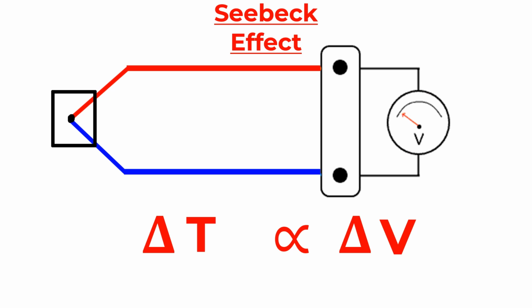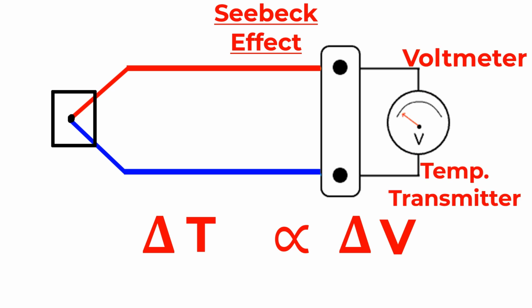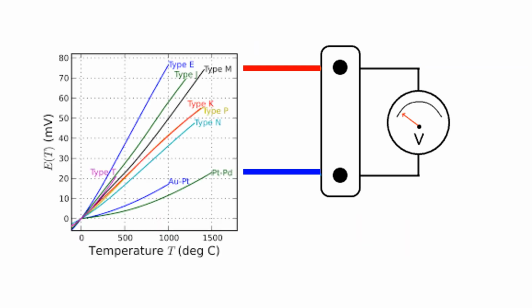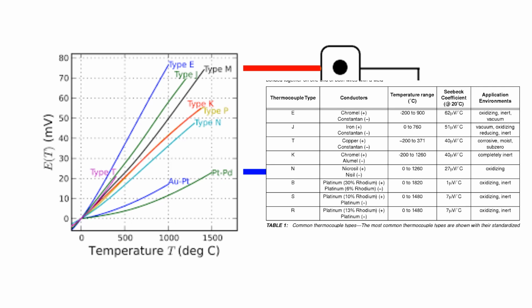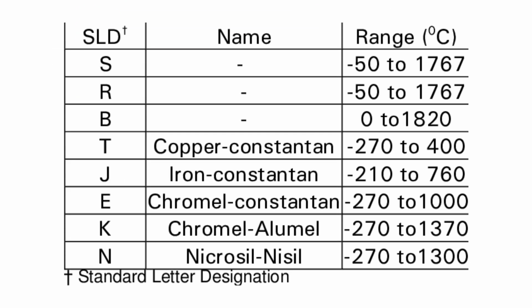To make practical use of this effect, engineers connect the thermocouple wires to a measuring device, such as a voltmeter or temperature transmitter. The device reads the tiny voltage and, using a calibration curve or lookup table specific to the thermocouple type, converts that voltage into an accurate temperature reading. Different combinations of metals produce different voltage-temperature relationships.